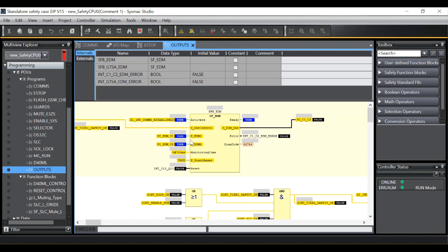Upon startup the outputs will be at zero. However, often the IO takes longer to establish itself on the network than the CPU takes to start running. This means that often we have a logic 1 on EDM 1 and EDM 2 and a logic 0 on the output. This is a fault condition for the EDM function block.